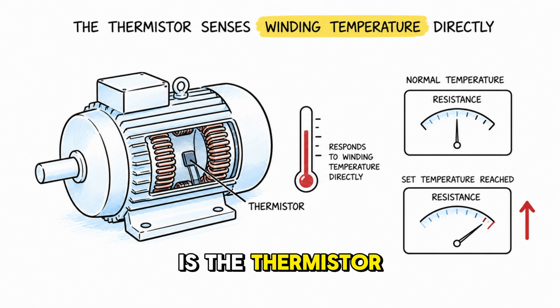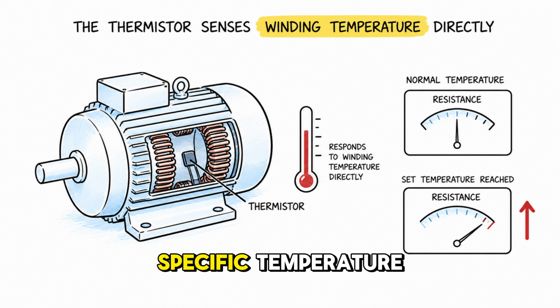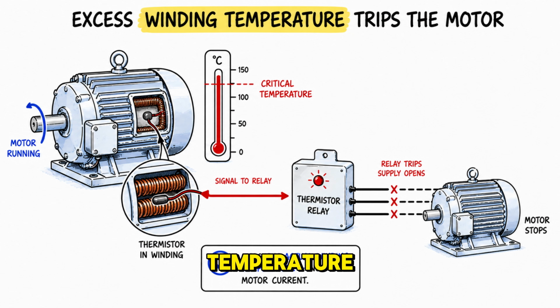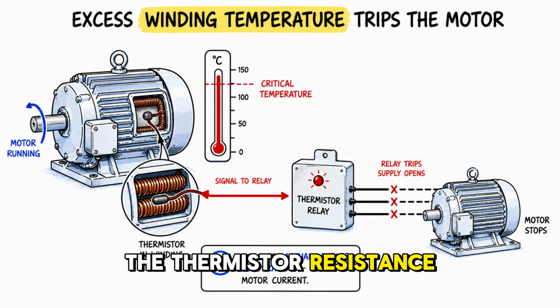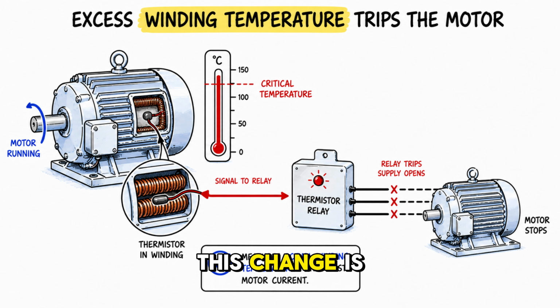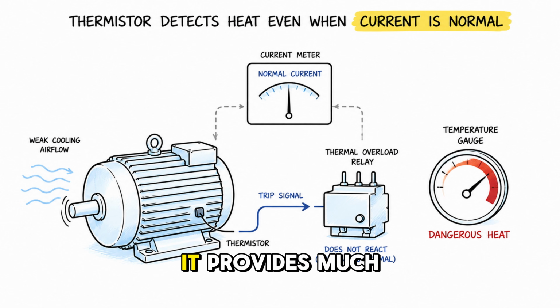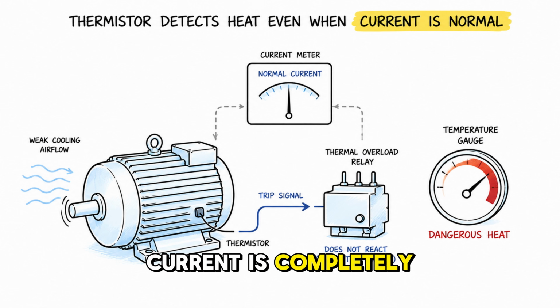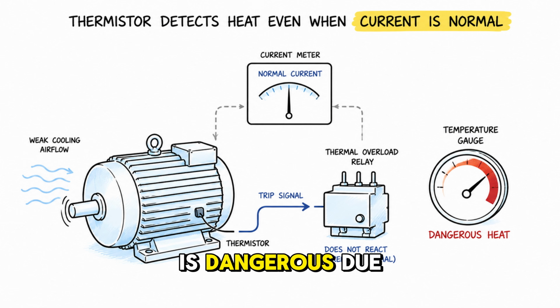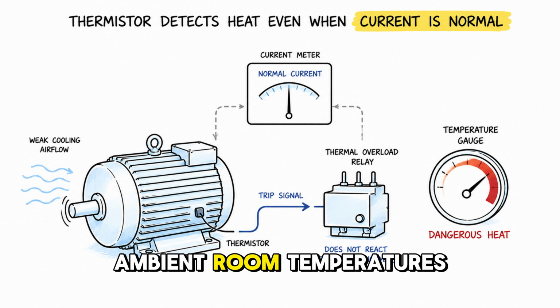The second device is the thermistor, embedded directly inside the motor winding. A thermistor is a temperature-sensitive resistor. Its resistance changes sharply at a specific temperature. When the winding temperature exceeds a critical threshold, the thermistor resistance changes dramatically. This change is instantly detected by an external relay that trips the motor. The thermistor measures the actual winding temperature rather than just inferring it from the current. For this reason, it provides much better protection than a thermal overload relay in situations where the current is completely normal, but the winding temperature is dangerous due to poor ventilation or high ambient room temperatures.